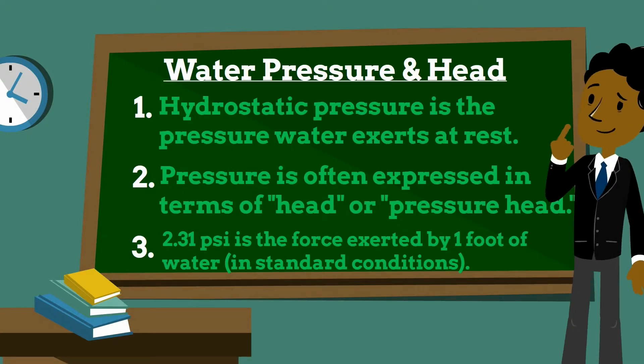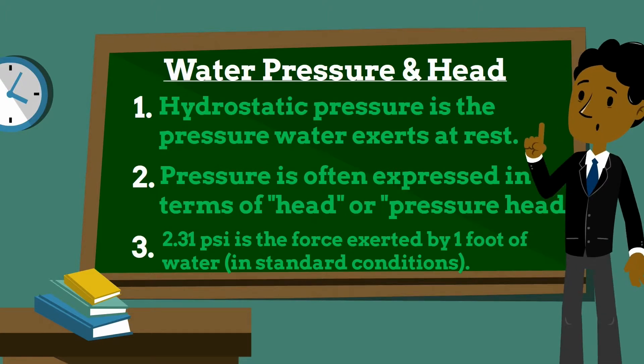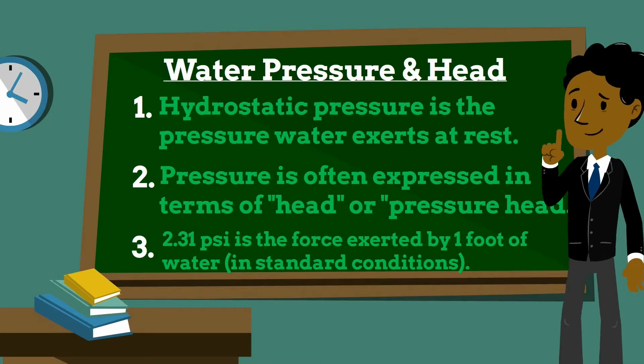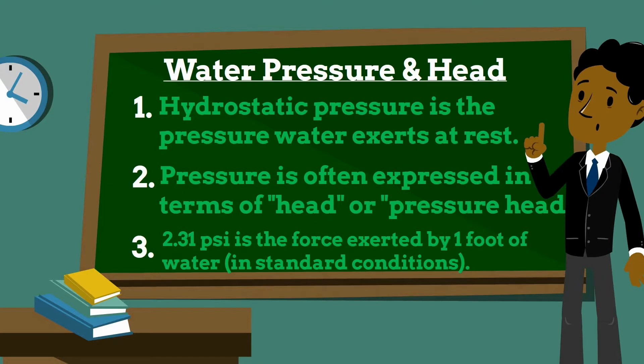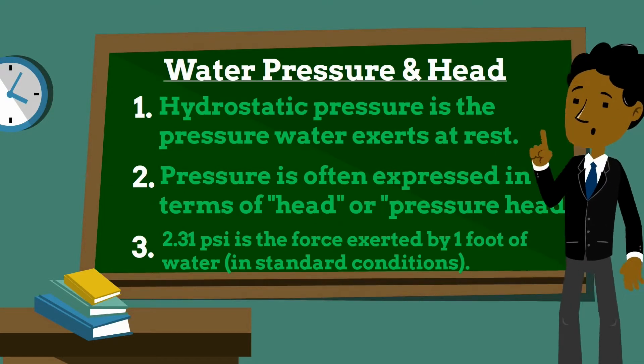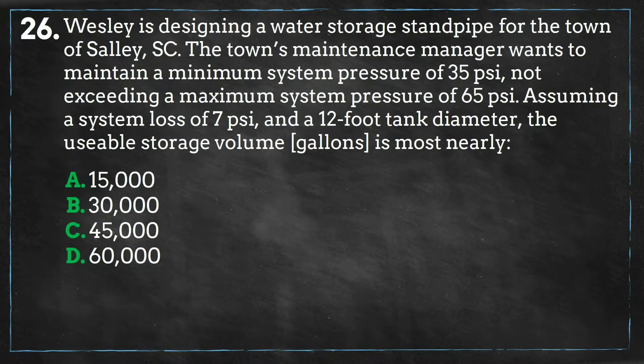This constant comes from the following: a square foot of area equals 144 square inches, and a cubic foot of ambient temperature water weighs 62.4 pounds. So if you pour one pound of water into a container occupying one square inch of floor space, that water would be 2.31 feet high.